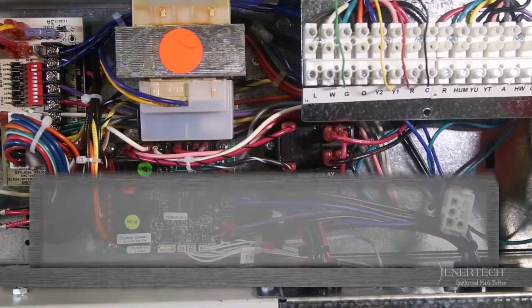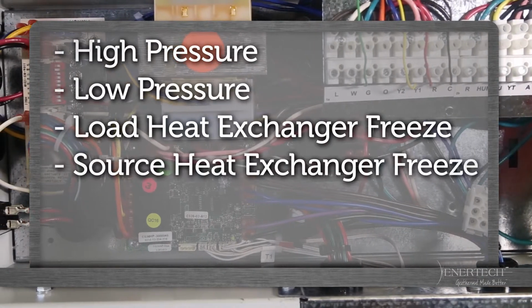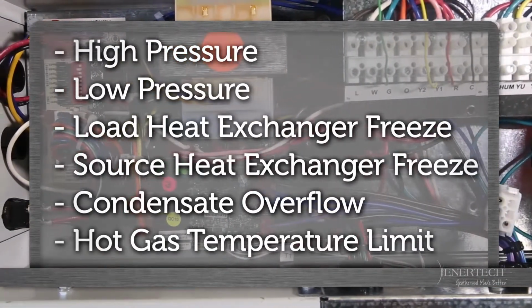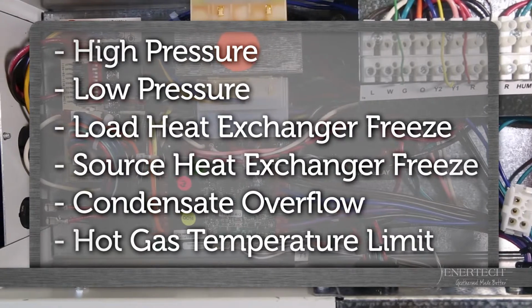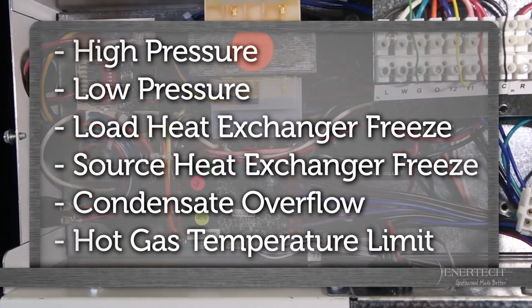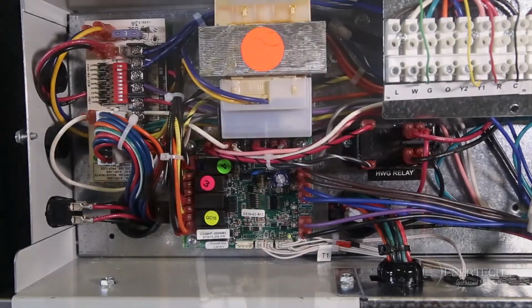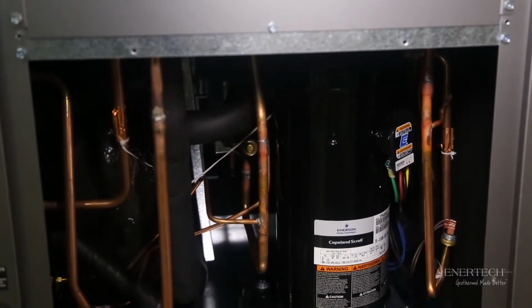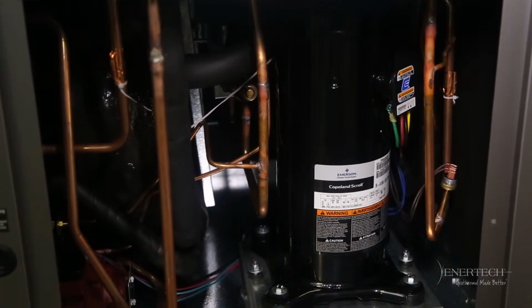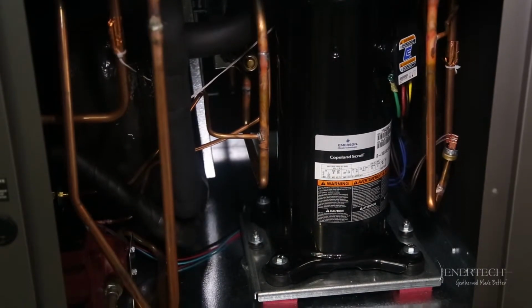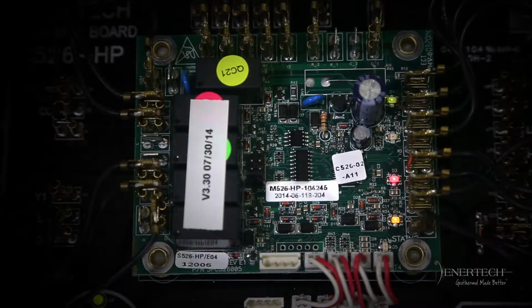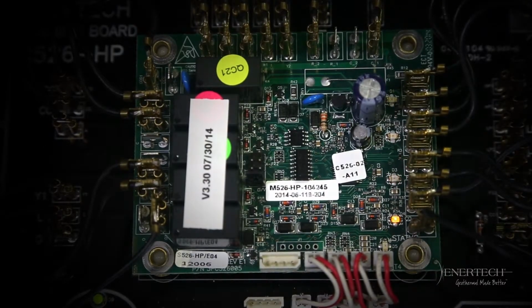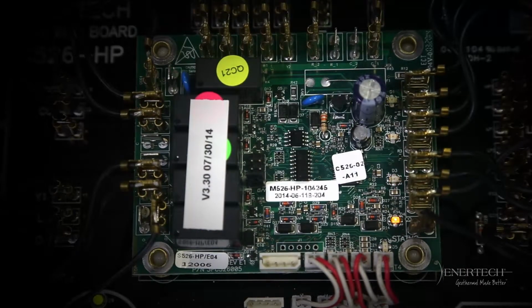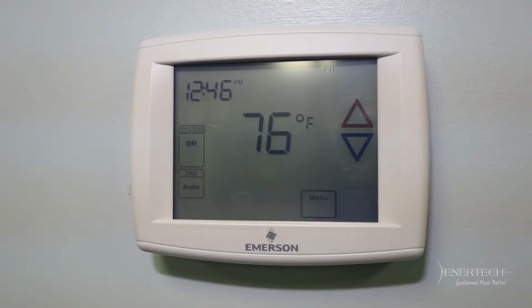The lockout board receives separate signals for high pressure, low pressure, load heat exchanger freeze, source heat exchanger freeze, condensate overflow, and hot gas temperature limit faults. After a continuous 30-second measurement of any fault, except the high pressure fault, the compressor operation is suspended. The high pressure fault is immediate. The appropriate LEDs flash for each fault. Once the unit is locked out, an output of 24 volts AC is energized on the L terminal for remote indication of a fault at the thermostat.